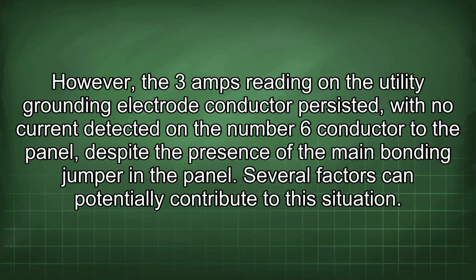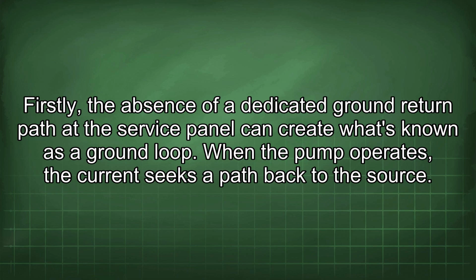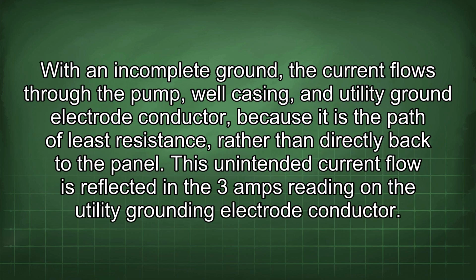Several factors can potentially contribute to this situation. Firstly, the absence of a dedicated ground return path at the service panel can create what's known as a ground loop. When the pump operates, the current seeks a path back to the source. With an incomplete ground, the current flows through the pump, well casing, and utility ground electrode conductor because it is the path of least resistance, rather than directly back to the panel. This unintended current flow is reflected in the 3 amps reading on the utility grounding electrode conductor.